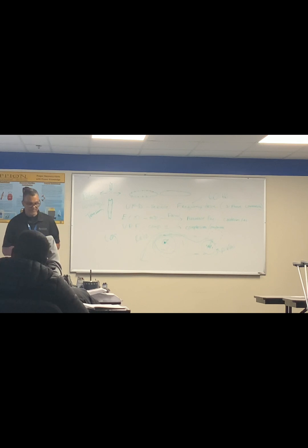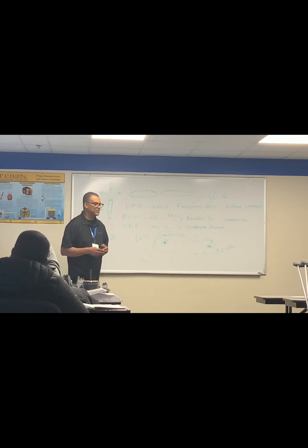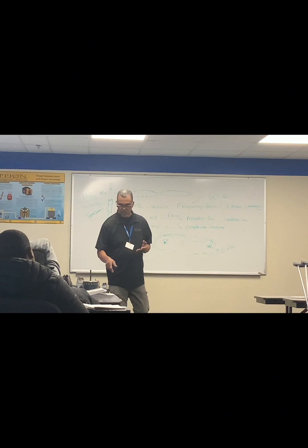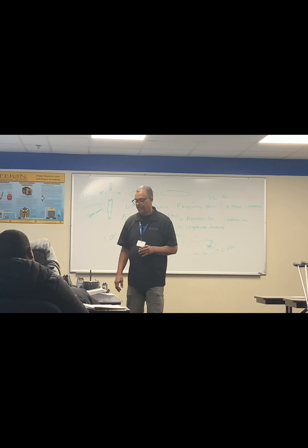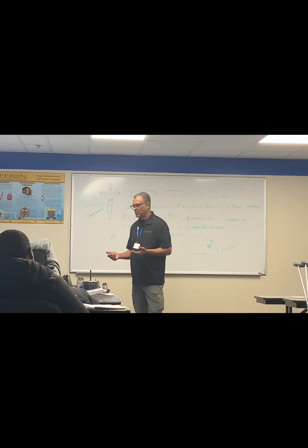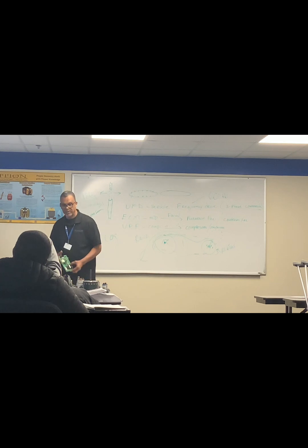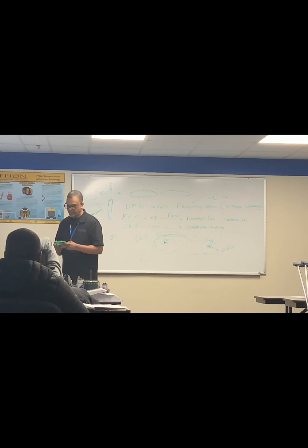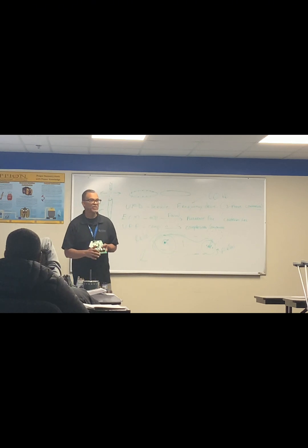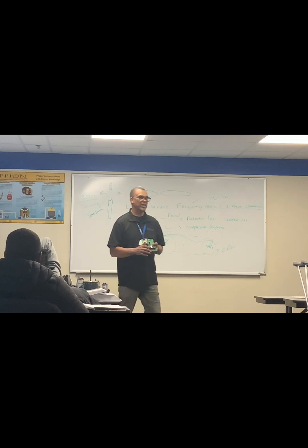Does it matter which side the brown wires on the capacitor go? Doesn't matter. One is going to be brown, one is going to be brown striped on this type. Two brown wires coming out, they go on either side. The rest of them go to the board, and one is going to be the speed, and then L1 goes on the other one on the board, and the other one will be on the speed. This is going to be neutral, so the neutral is going to go here. Everything neutral is going to go to the neutral.